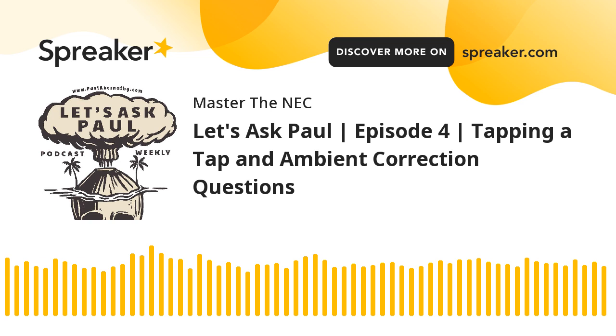Now, the next question I get from people is, can I put 20 amps on a 20 amp breaker? In general, yes, as long as it's not a continuous load. I can put 20 amps on a 20 amp breaker every day of the week, as long as it's not a continuous load. Now, we're not talking about receptacle limitations and other things that limit receptacle applications when cord and plug connected things are involved. We're just talking general statement here.